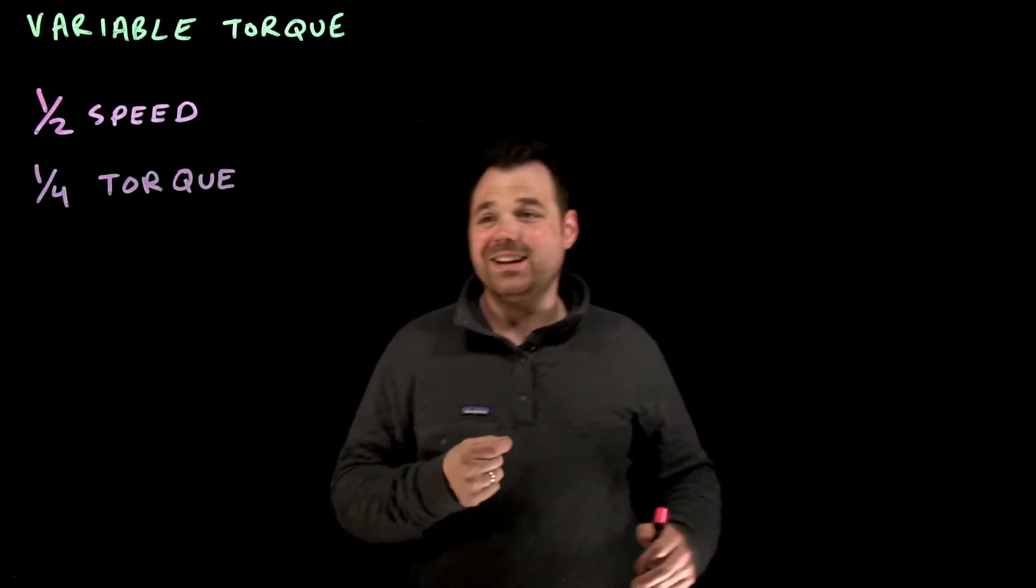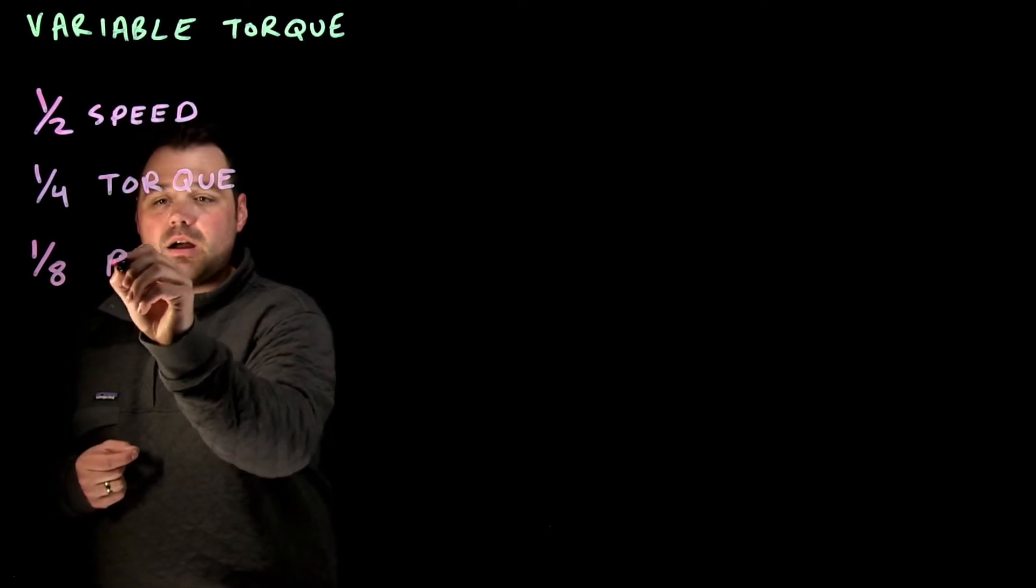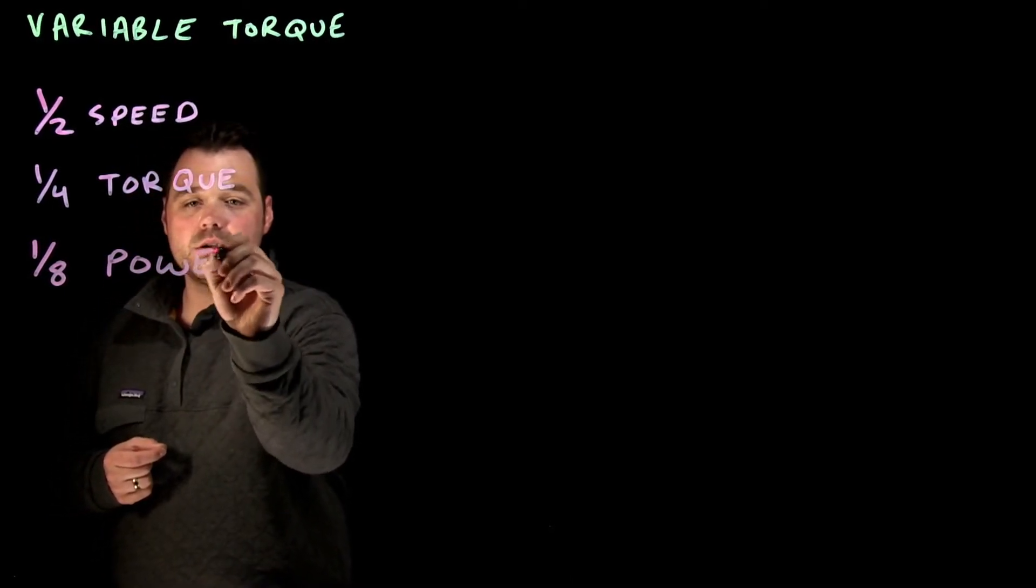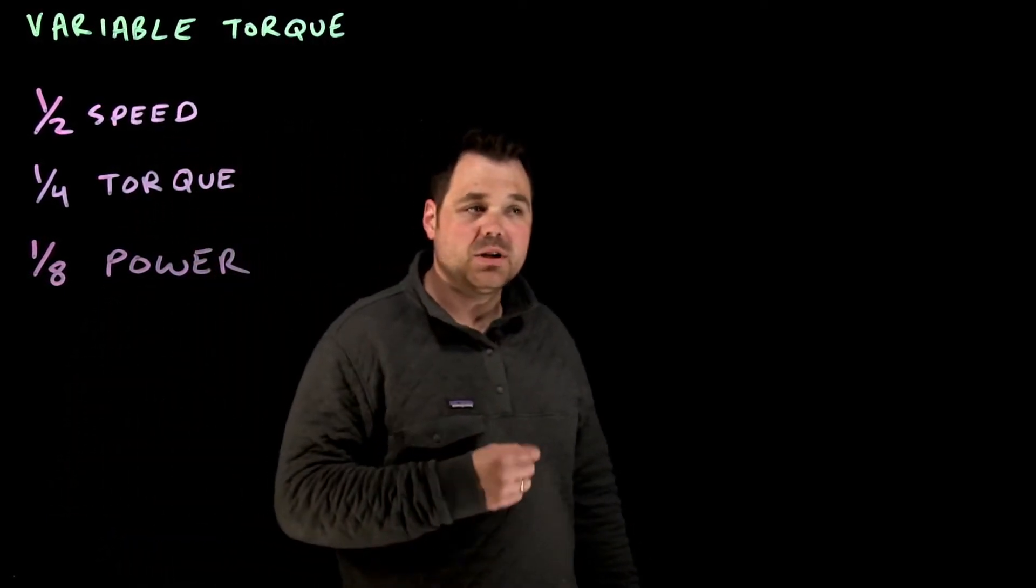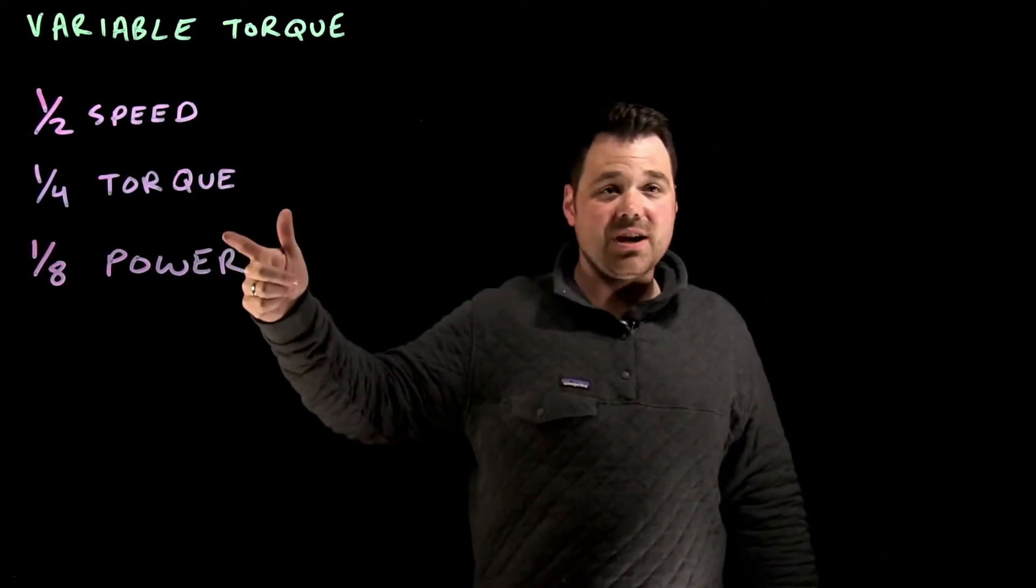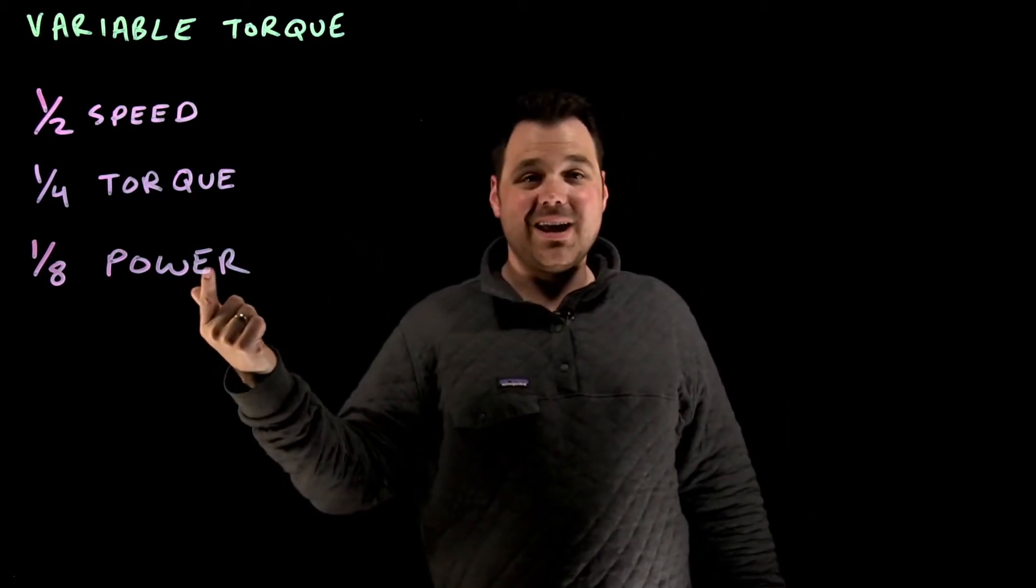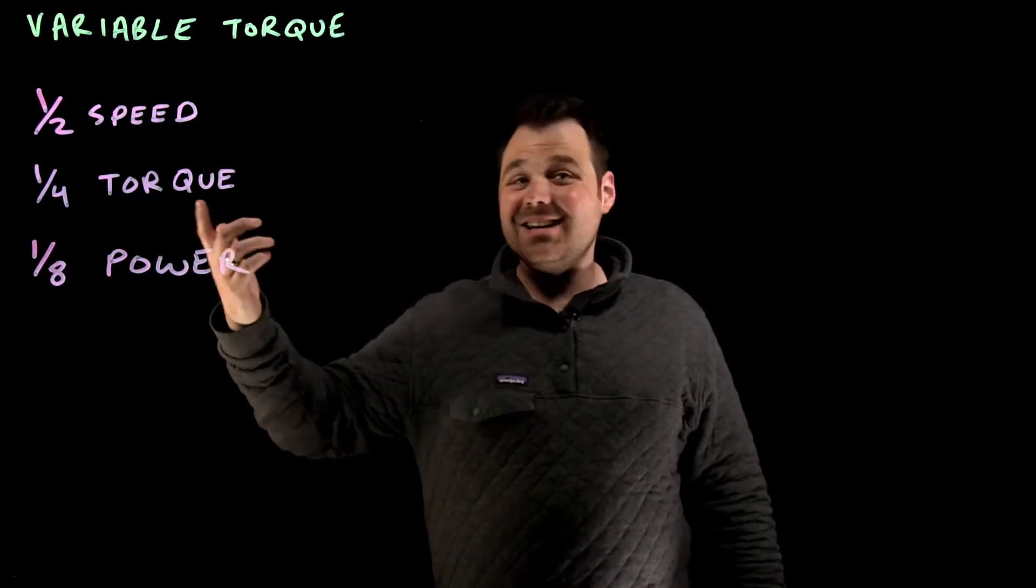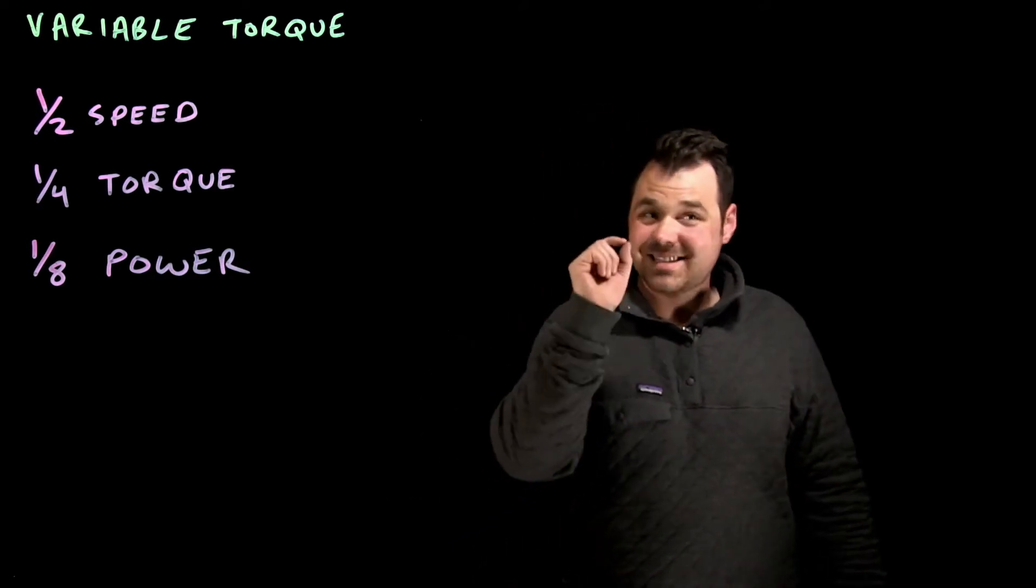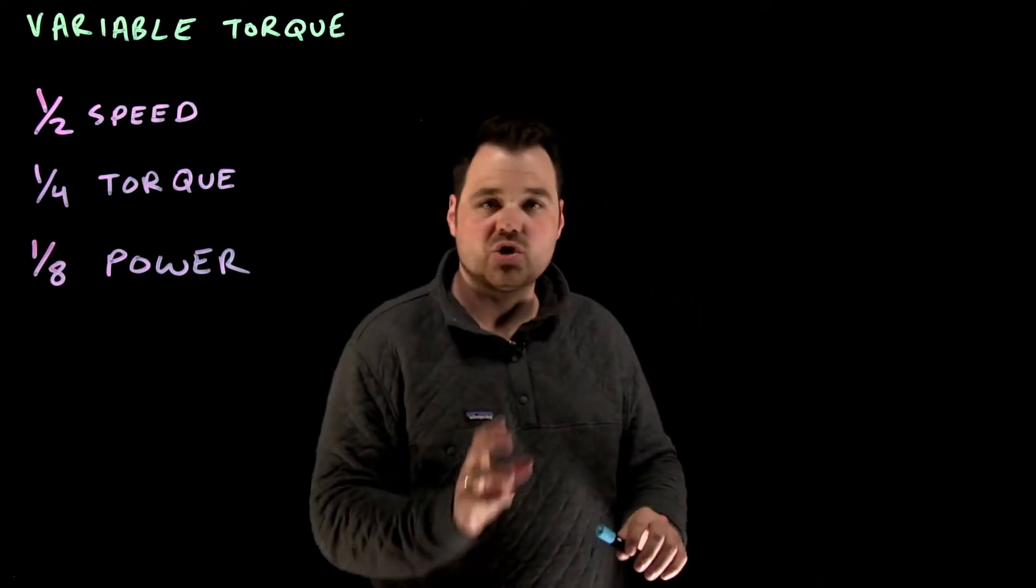Well, that's going to translate into only requiring one eighth of the power input required. So that's a huge savings. If I only need to run my motor at 50%, because that only requires a quarter of the torque, that's going to be an 87.5% savings in power.